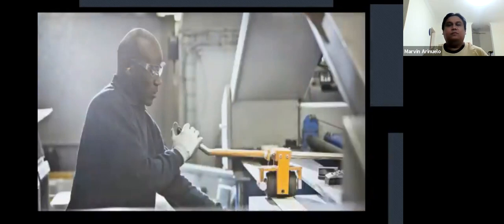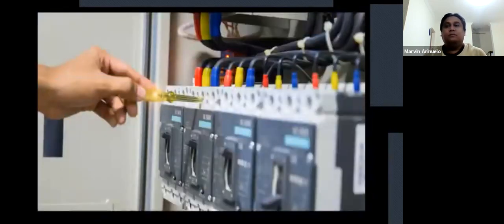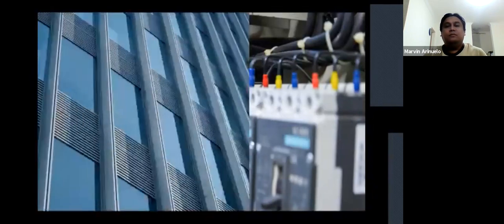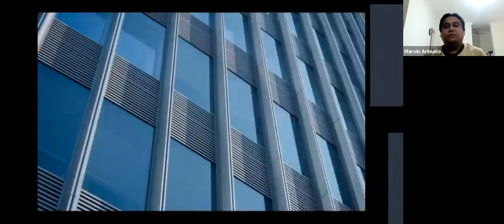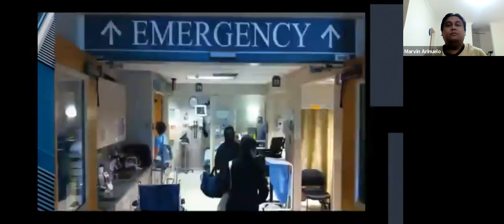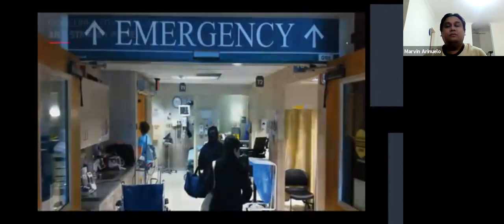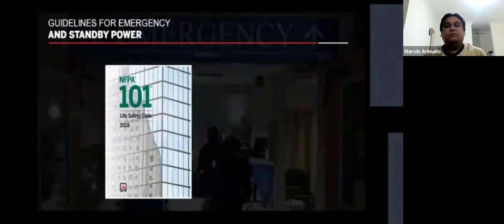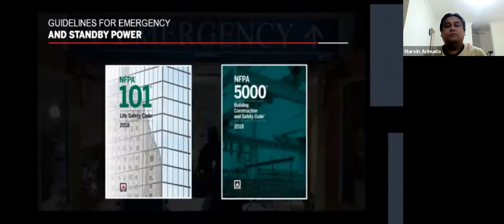Based on a building's occupancy, life safety and building codes, as well as some standards, may require standby or emergency power. Section 20 of the FPH mentions the need for these power systems in occupancies such as high-rise buildings and healthcare facilities as required by NFPA 101 Life Safety Code, and NFPA 5000, Building Construction and Safety Code.